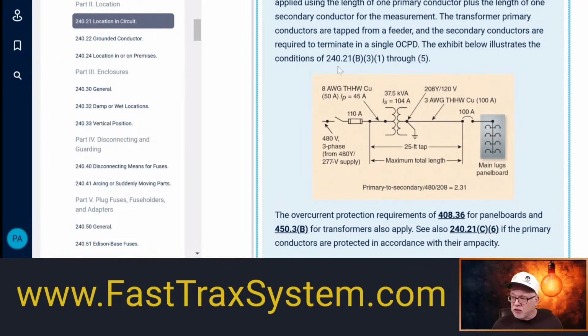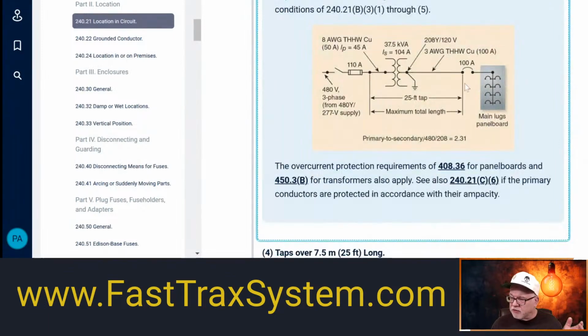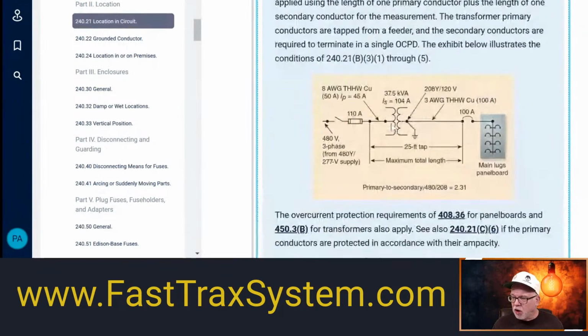Then we kick into the 25-foot, and we know that all this is okay, that this panel board and these loads are sized right. This transformer can handle 104 amps. It's got a 100 amp overcurrent device. It's got 100 amp rated wire, and they've done a load calculation. And this panel board is protected in 408.36, okay, at its rating. So this is 100 amp, okay. So these calculated loads are not going to exceed the 100 amps, okay. So all of this is perfectly fine, and this scenario has been all sized out.